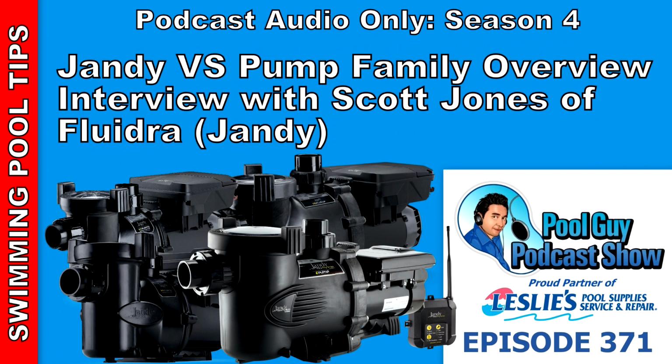And they all also feature, again, this is specific to our DV2A models, what we call a zero clearance TEFC motor. Most TEFC motors out in the market pull in the cooler air from the back of the motor. So if you're in really tight spaces and you put a typical TEFC motor up against a foundation or a fence, you're going to overheat that motor because it's not getting sufficient airflow. Our zero clearance TEFC motors pull in the cooler air from the sides of the drive, from the fan. So regardless of how tight it is up against a tight space, you're going to get sufficient flow for cooling.